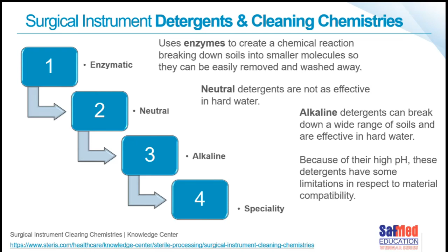Alkaline detergents can break down a whole range of soils and can be very effective in hard water, but they have a higher pH, so they have some limitations. We tend to use them not with manual cleaning but in an automated washer disinfector - not the only detergent one can use there, but that's the tendency. You also have to be aware of their limits, because there are material compatibilities or incompatibilities that can become a problem. Certain things like aluminiums don't respond well to alkaline detergents, so it's very important to take this into consideration.